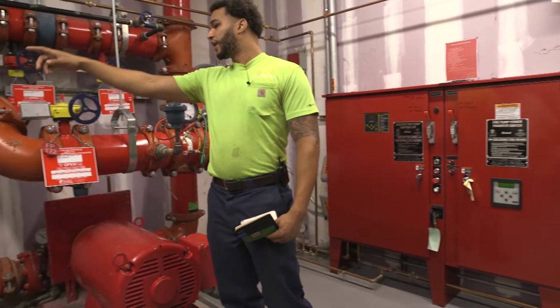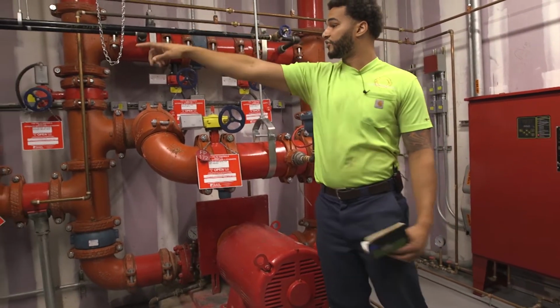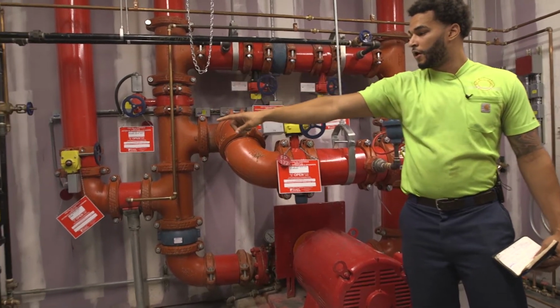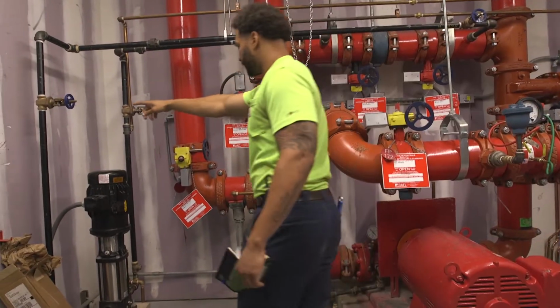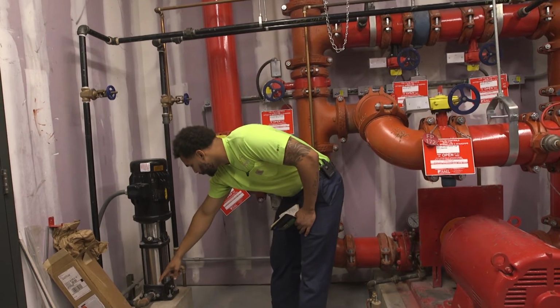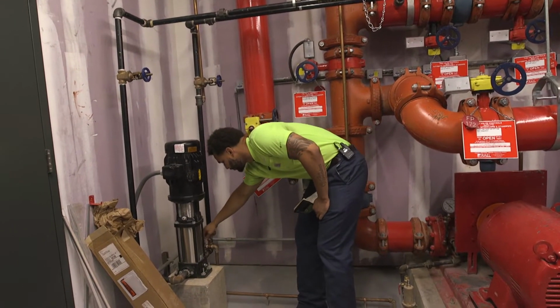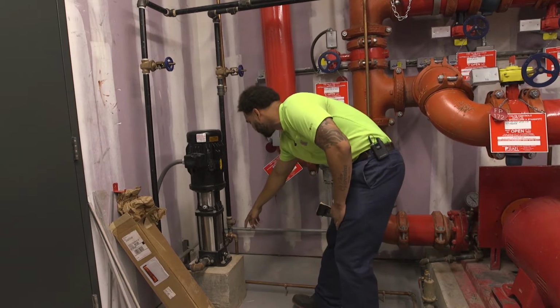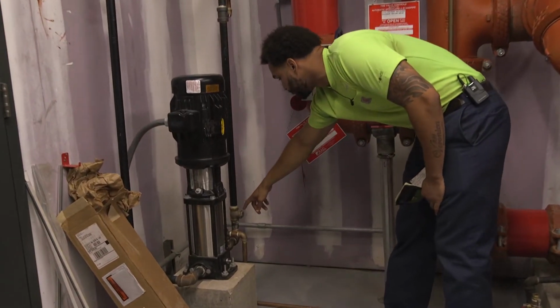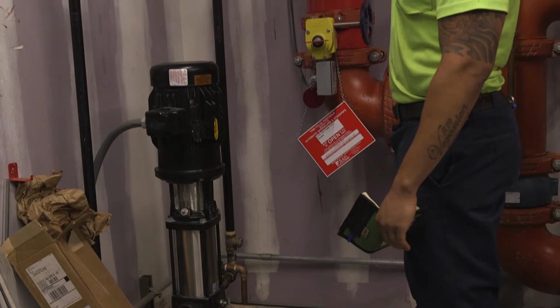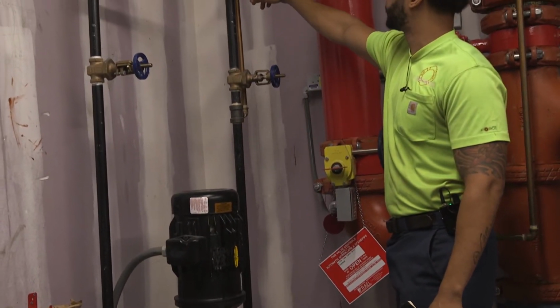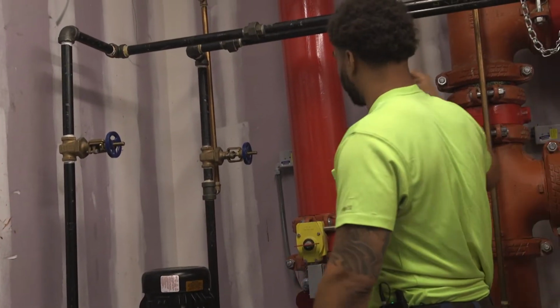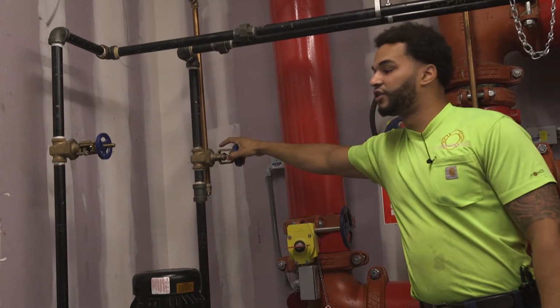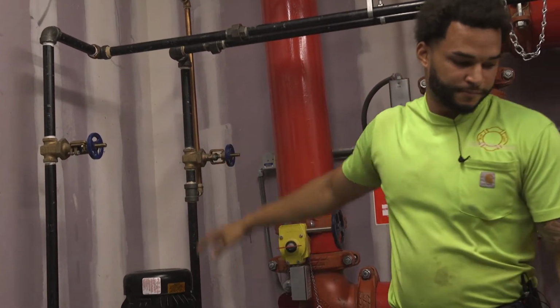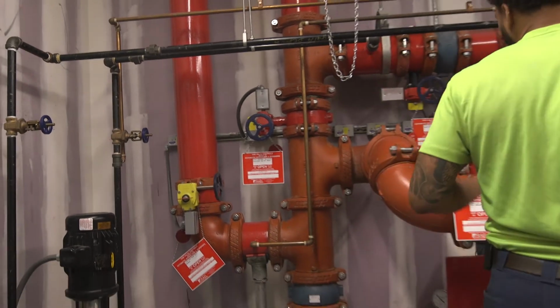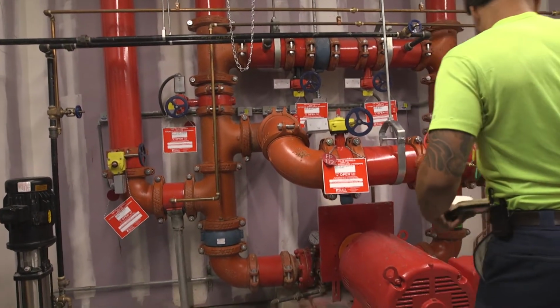So on the jockey pump side, we have our suction side. We have our suction side isolation valve there. So if we keep following, we have our pressure going into the pump. So here we have a casing relief valve for the jockey pump here. If we keep following the discharge, now we have our discharge side check valve. If we keep going up, here we see our sensing line to read our jockey pump pressure, and we have our jockey pump isolation valve here. All those valves will always be in the normally open position as well.